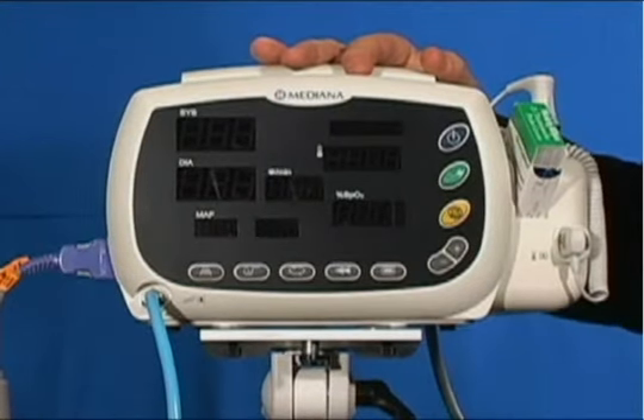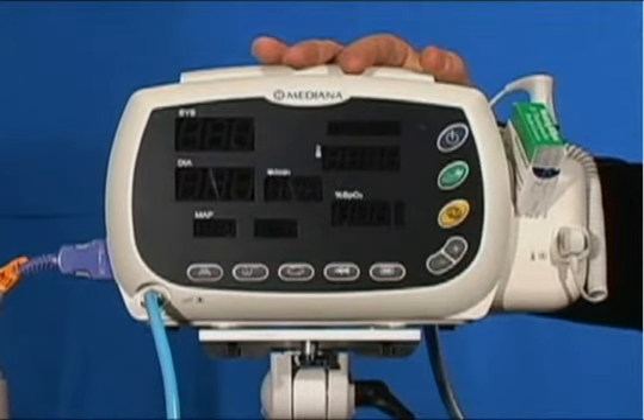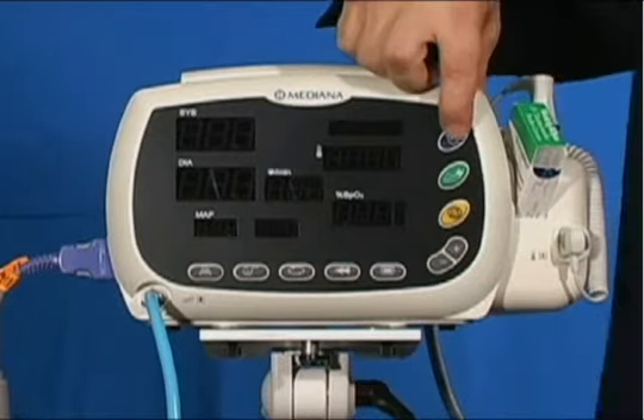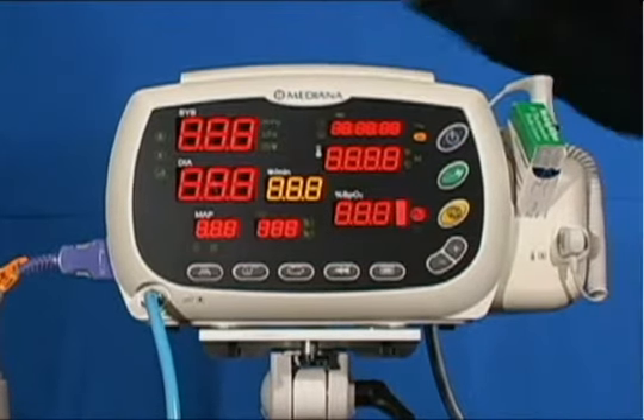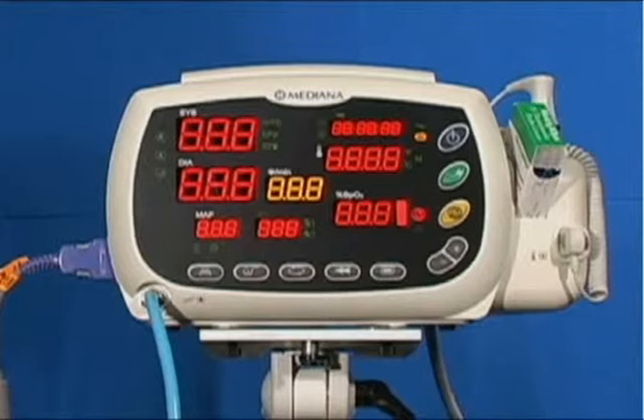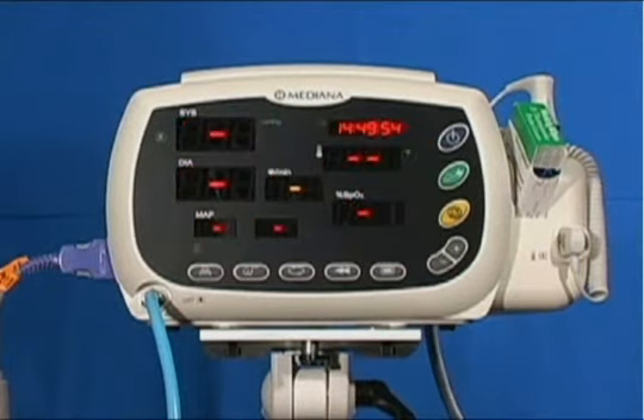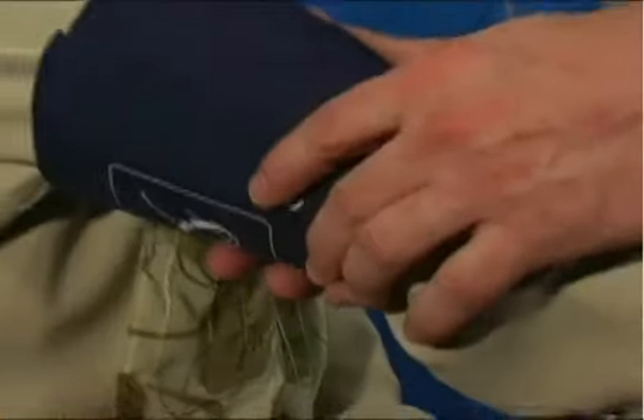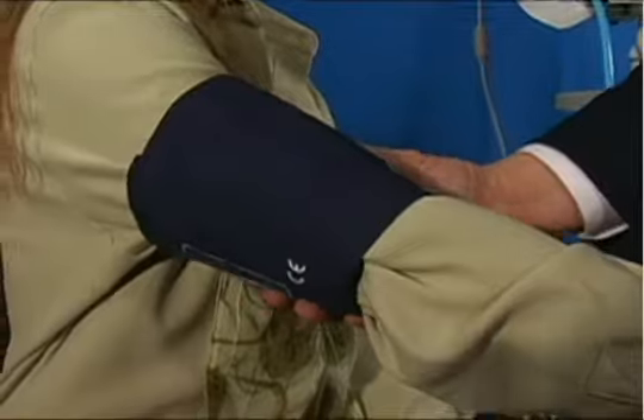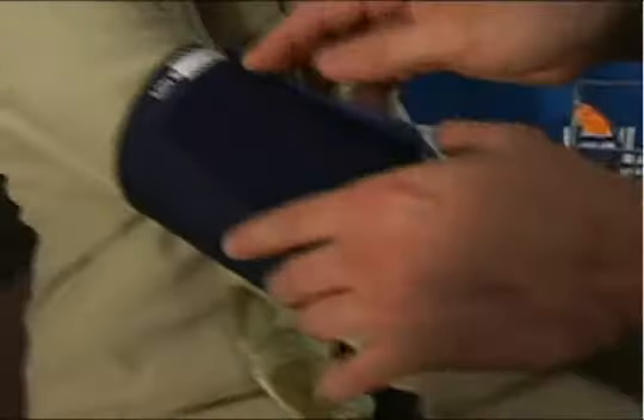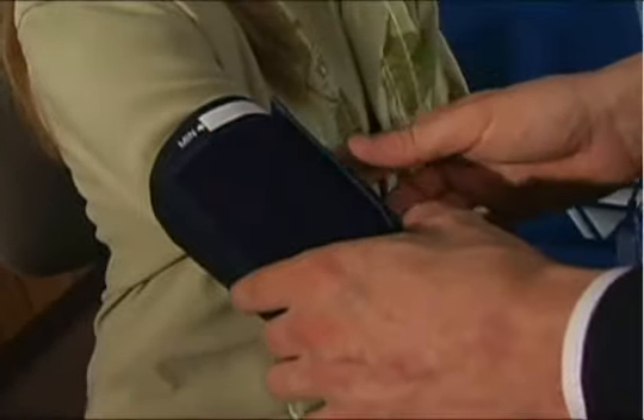The operation of the MEDIANA YM1000 vital signs monitor is real simple to use. Turn on the power, I press the blue button and hold it in. The monitor comes on and it goes through a self-check. Now to begin non-invasive blood pressure monitoring, first we apply a blood pressure cuff to the patient's arm. We want to make sure that the cuff is the right size, and we're looking to make sure that it's in the right cuff range between the minimum and the maximum.